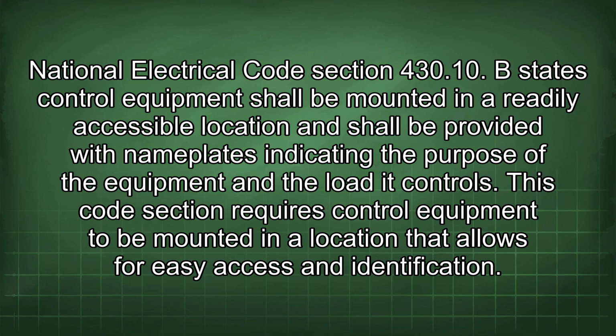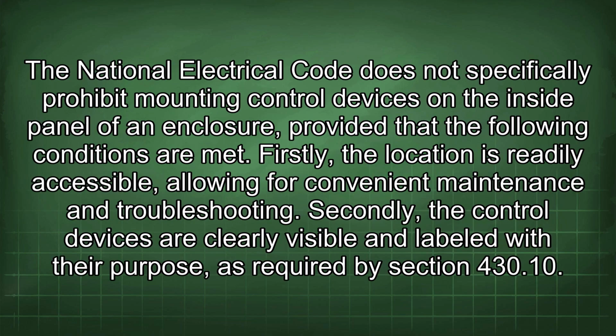This code section requires control equipment to be mounted in a location that allows for easy access and identification. The National Electrical Code does not specifically prohibit mounting control devices on the inside panel of an enclosure, provided that certain conditions are met.